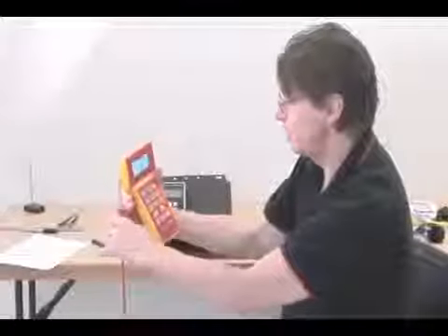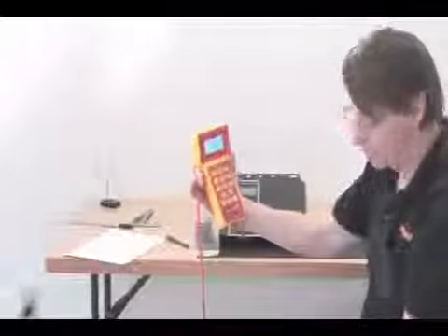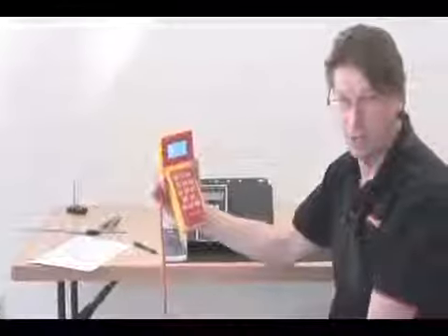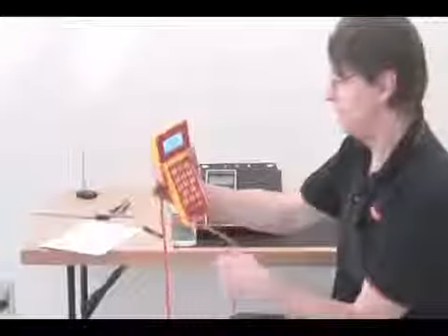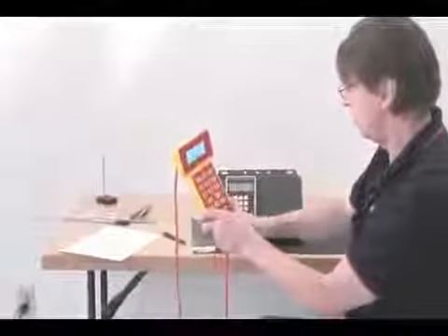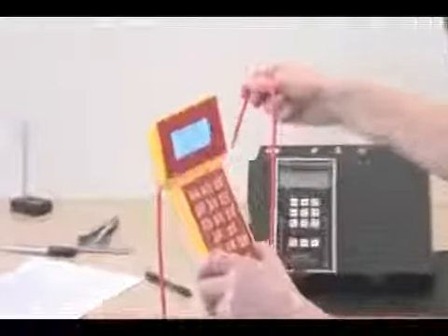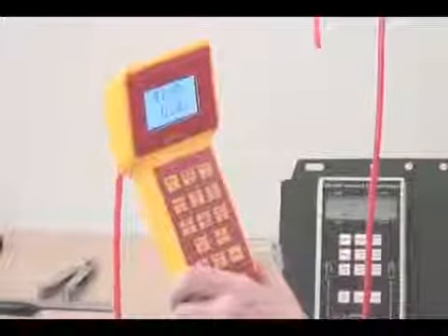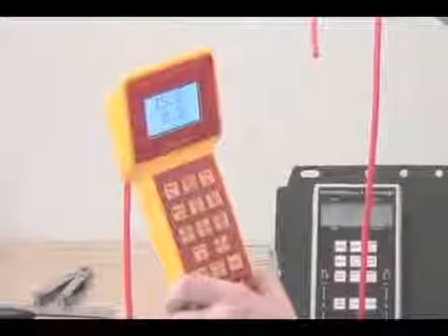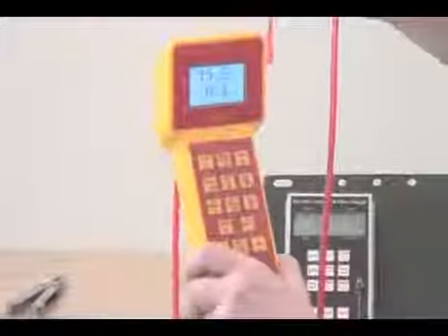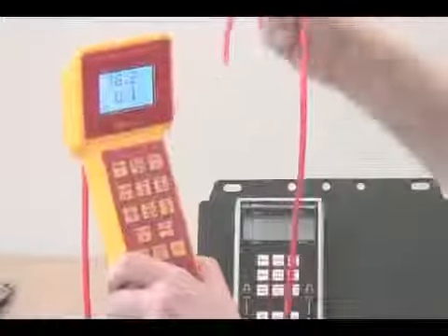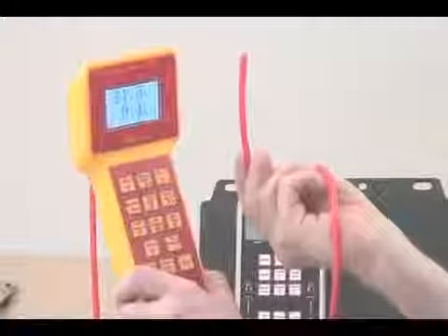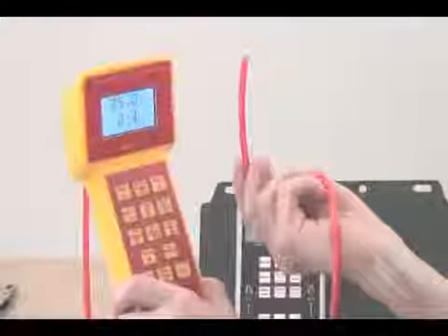So other problems that we'll often run into is the water in the tube problem. Now earlier we showed dipping a tube into the water and creating a pressure, but if we have a water drop in the end of our tube here, it will actually create a pressure, and I'll just show you. So what I've done here is I've got a water drop in the end of the tube, and look at that, I've got a 15 pascal pressure there. You can see the water drop just dropped off, and I think the water drop is still in there. And if we change it from going up or down, it should change the pressure. There, the pressure's gone up.